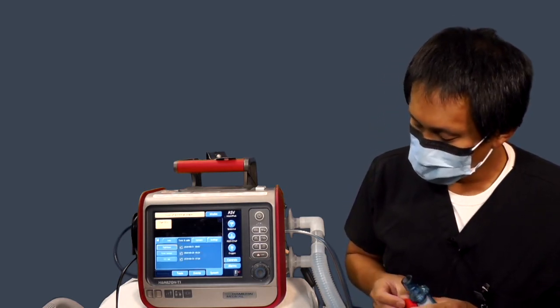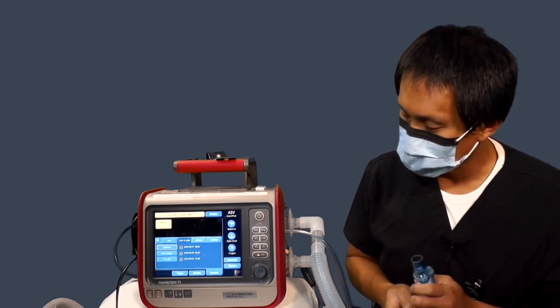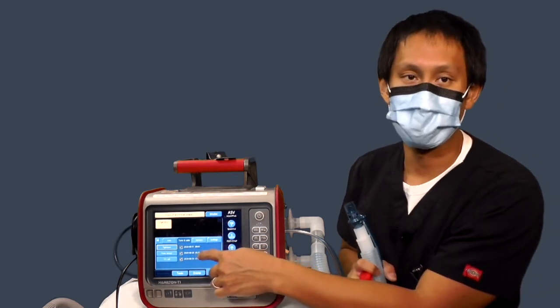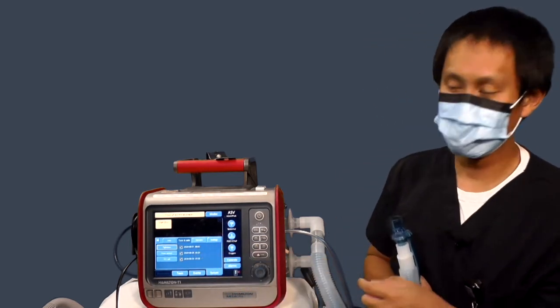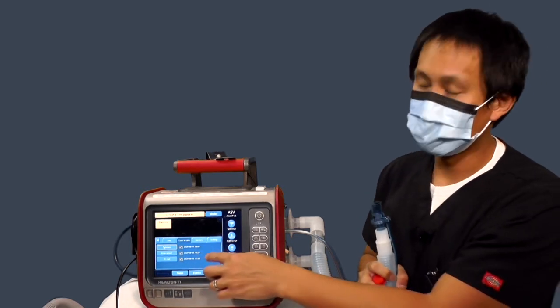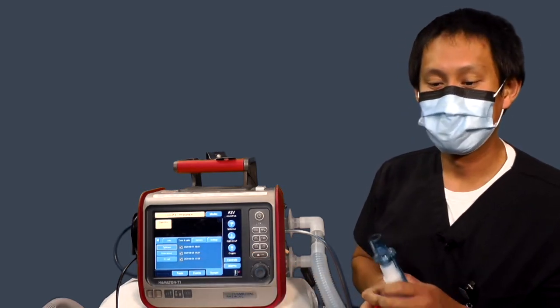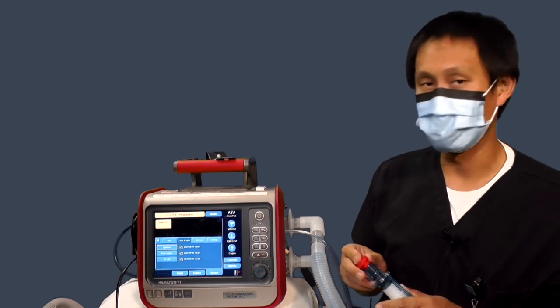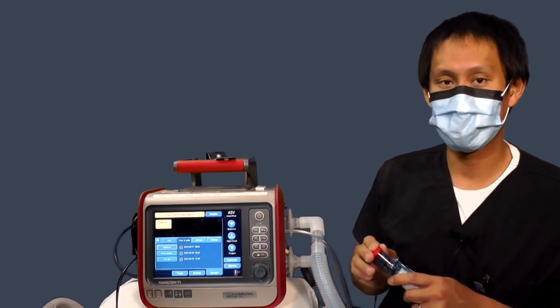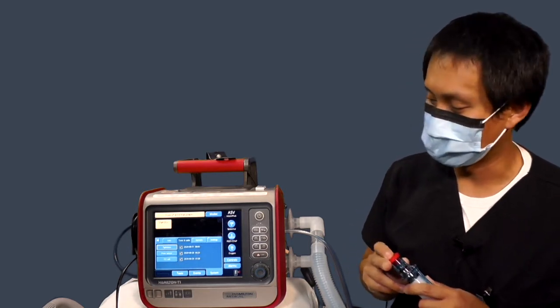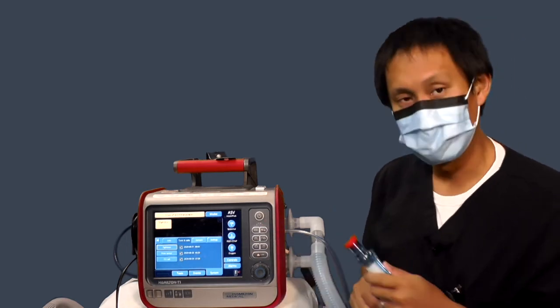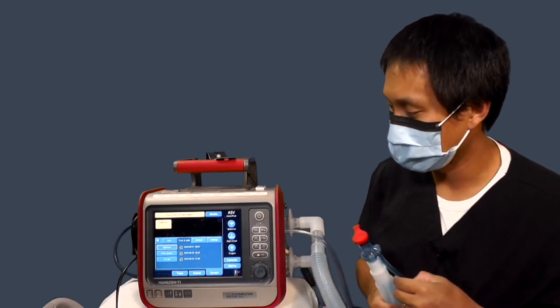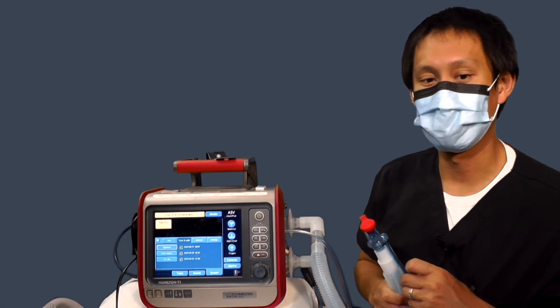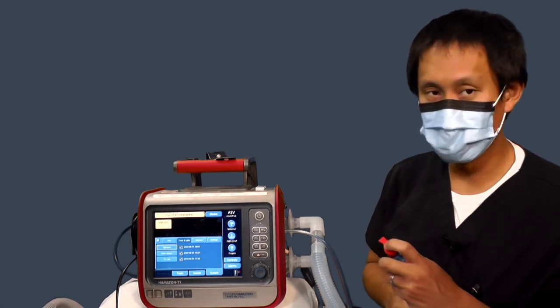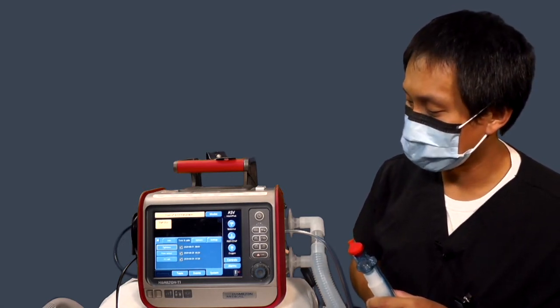Okay. When it's completed, it will either pass or fail. If you pass, you'll get this green check mark. If you fail, you'll get a red X. It'll timestamp when it was last done. So if you come across a ventilator and you don't know if it's been calibrated or not, and it has a circuit hanging off of it, you can pull up this test and calibration menu and it'll tell you when it was last done. So that was it with the tightness check.